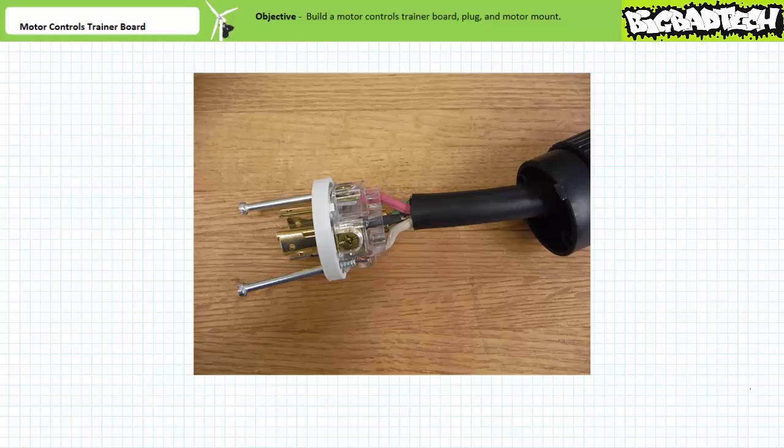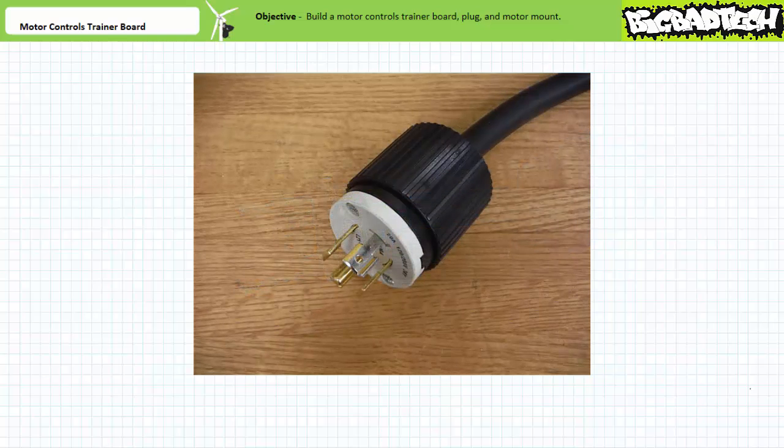Note applied phase sequence dictates the direction of rotation of an industrial three-phase AC motor. Make sure all plugs are wired consistently if you're working with a group, so that way there are no surprises. Next, slide the dust cap on and tighten the plug head.